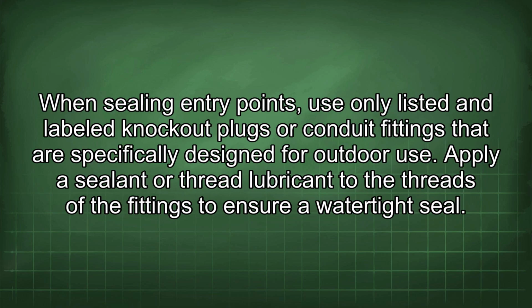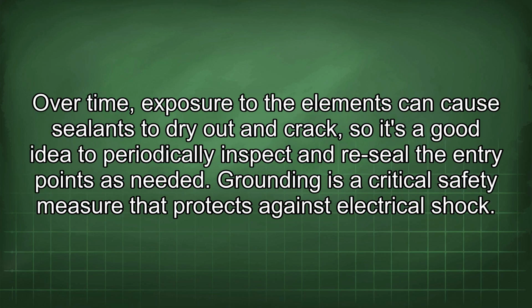When sealing entry points, use only listed and labeled knockout plugs or conduit fittings that are specifically designed for outdoor use. Apply a sealant or thread lubricant to the threads of the fittings to ensure a watertight seal. Over time, exposure to the elements can cause sealants to dry out and crack, so it's a good idea to periodically inspect and reseal the entry points as needed.